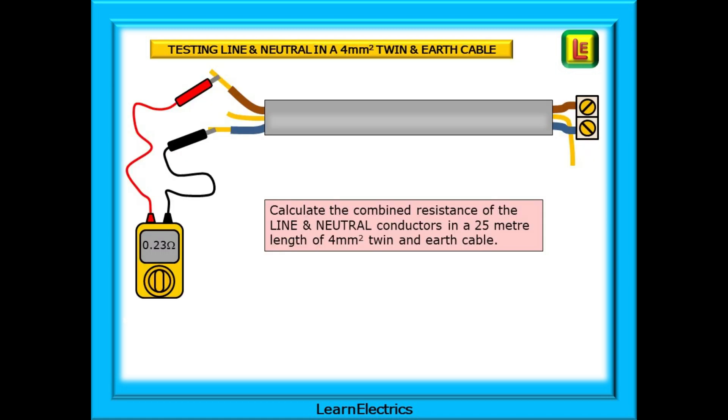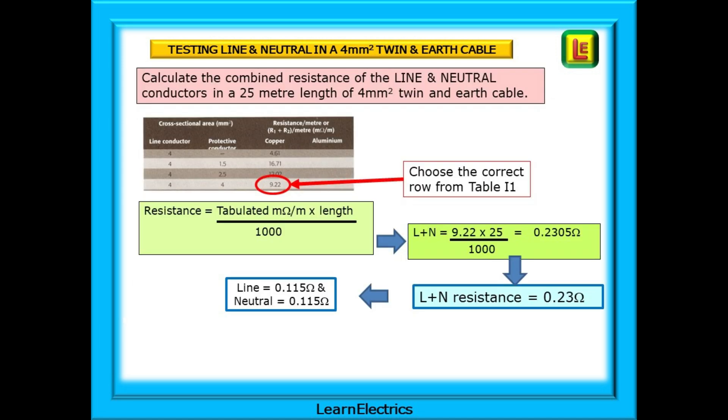We might be asked to check the combined resistance of the line and neutral in a 25 meter radial circuit incorporating 4 millimeter twin and earth cable. And this can be easily achieved by linking the two conductors at one end and testing at the other. Now we must choose the correct row in the table. 4 millimeter and 4 millimeter has a milli-ohm per meter value of 9.22 milli-ohms per meter length. The resistance of L plus N is 9.22 times 25 and divided by 1,000.